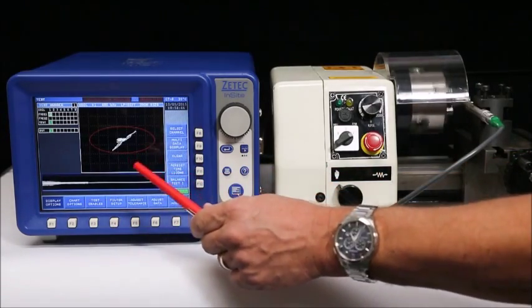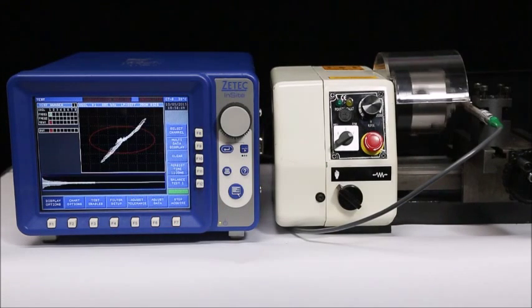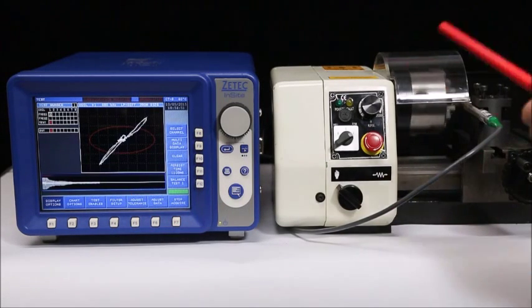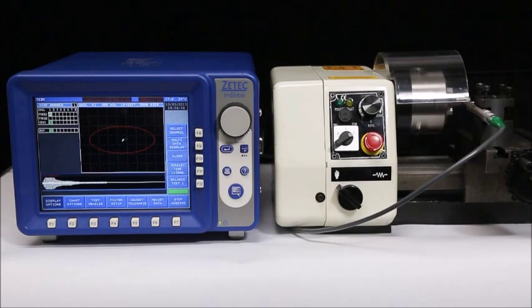As I continue it's going to exceed the alarm limits in red, create an audible as well as a digital output to your PLC to trigger a reject gate.